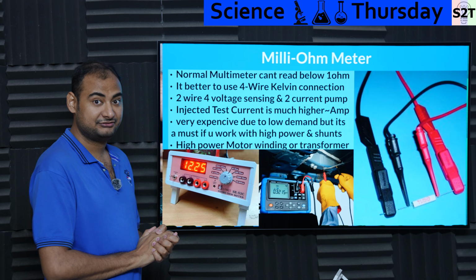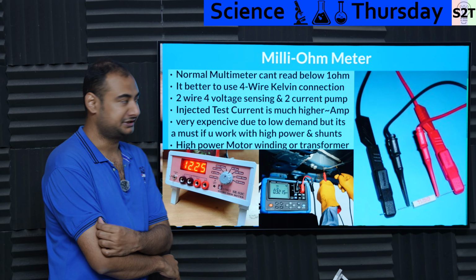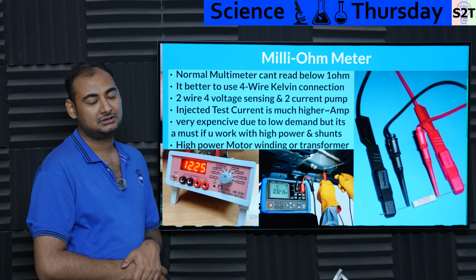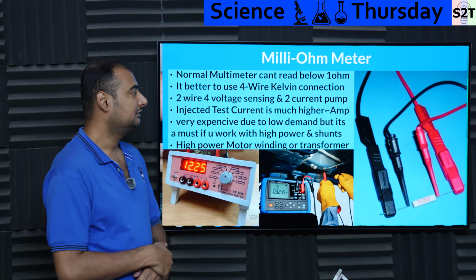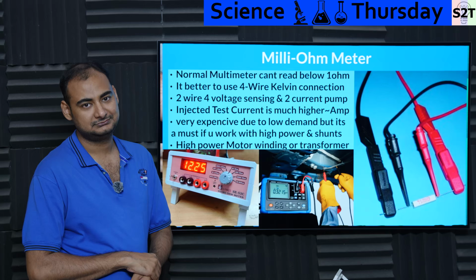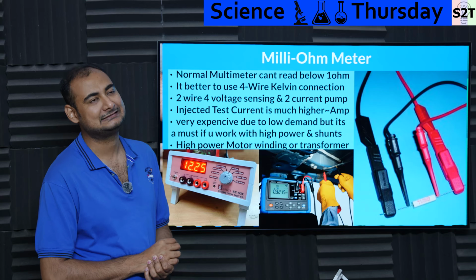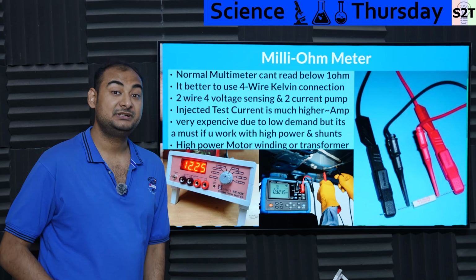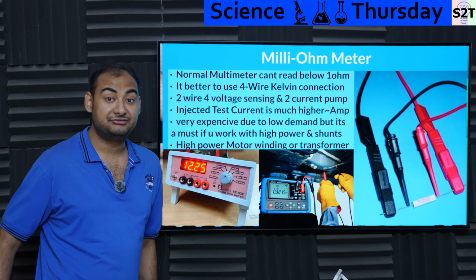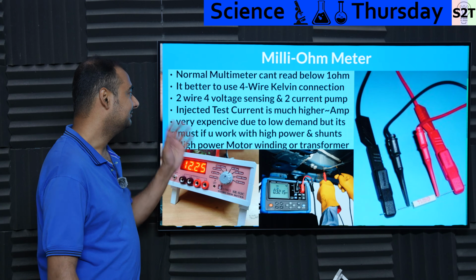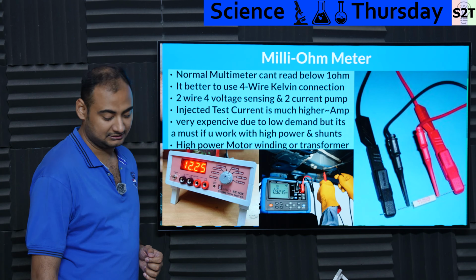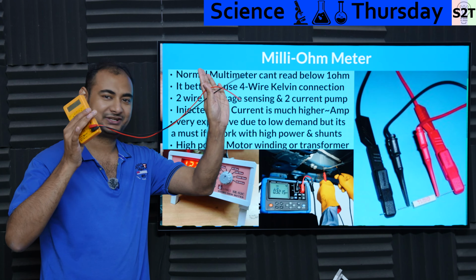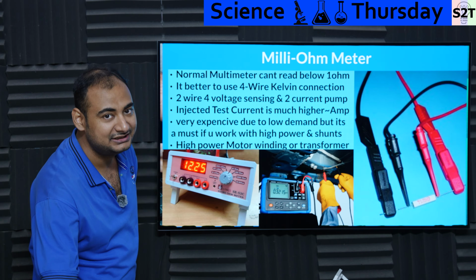So let's dive deep into the first one, which is the milliohm meter. Now, a normal multimeter, it does not matter which brand, will generally not go below 1 ohm. If you go below 1 ohm, it will try to, but it will not be trustworthy. And again, it's a physics problem. You cannot bypass it because generally all meters are designed for basically only 2 probes. That's not good enough. You need 4 probe wiring, basically this sort of system.